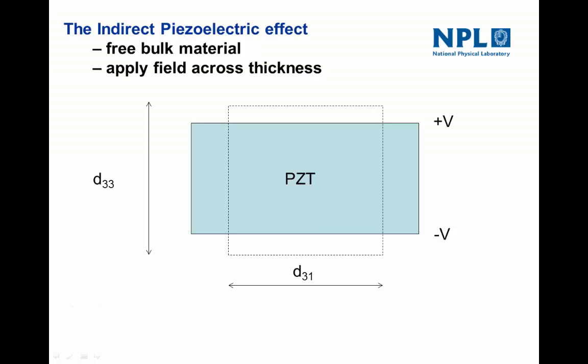If we start by looking at what happens to a piezoelectric material when you apply a voltage to it — in this case we've got a piece of PZT floating in space with a voltage applied on top and bottom — you can see it changes shape, shown by the dotted lines. It expands in one direction which we call the D33, and it contracts in another direction which we call the D31, and these are the piezoelectric coefficients which define how active that piezoelectric material is. That's essentially what we want to measure for thin films.